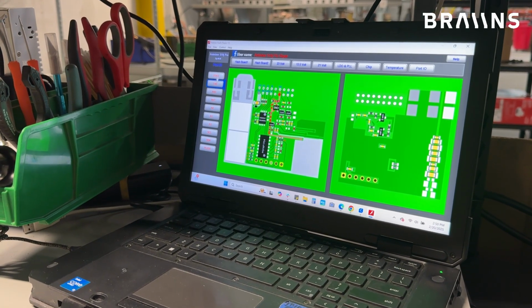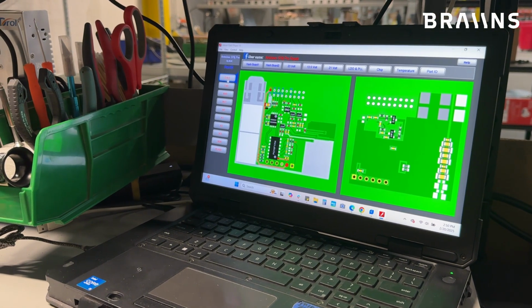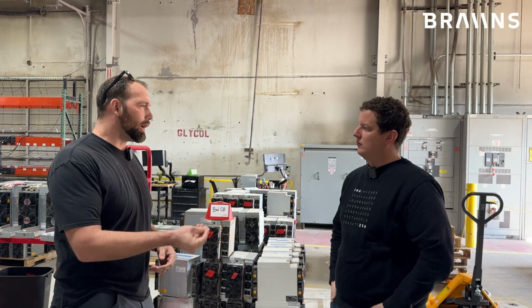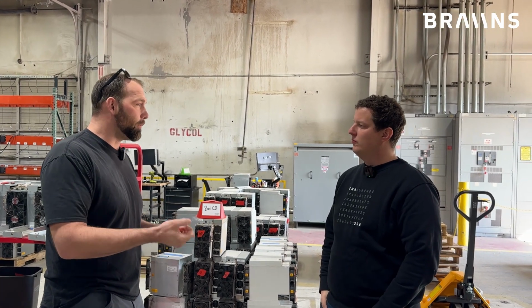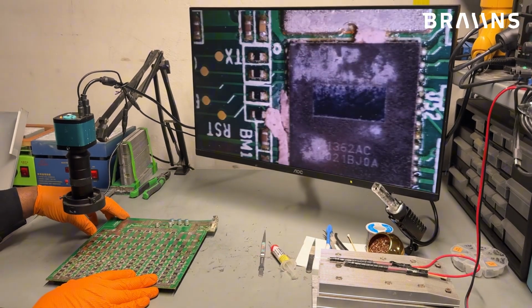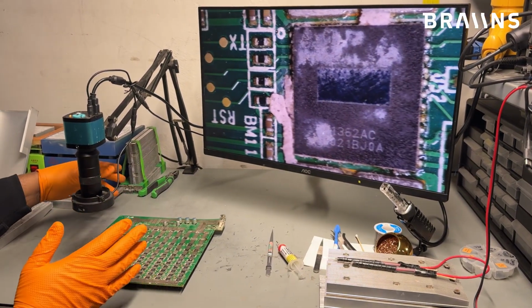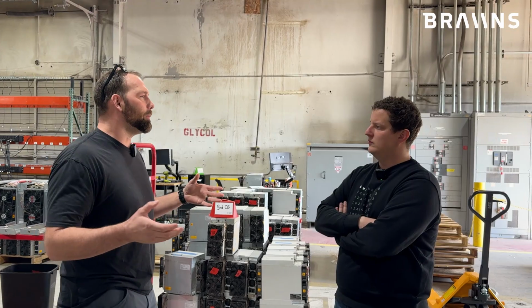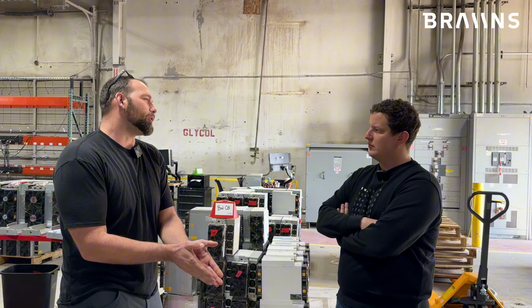Even measuring on the smart PDUs, there's a bit of line loss, and so we also compare that and average it to an amp clamp measurement. We actually build custom cords, so we put a clamp over there and measure the amperage going through the power cord itself. I would say it was a good case study, and from there we're able to say, hey, these firmwares do X, Y, and Z, and then be able to compare them side by side, so whether that's for us or our client, we can recommend, hey, this is the best one for this situation.